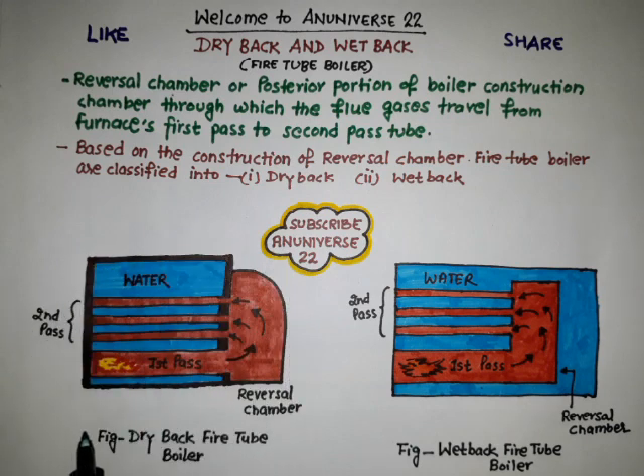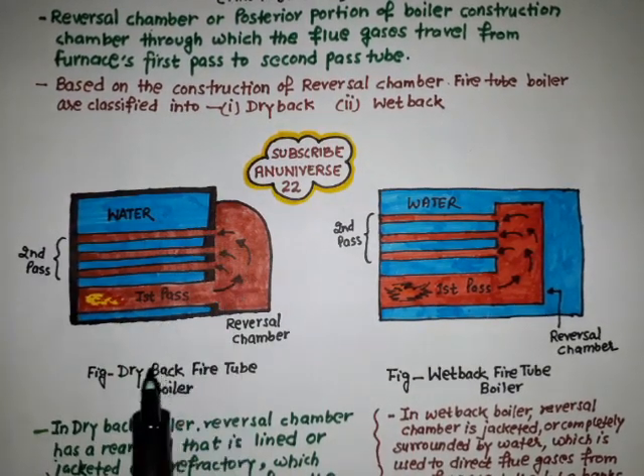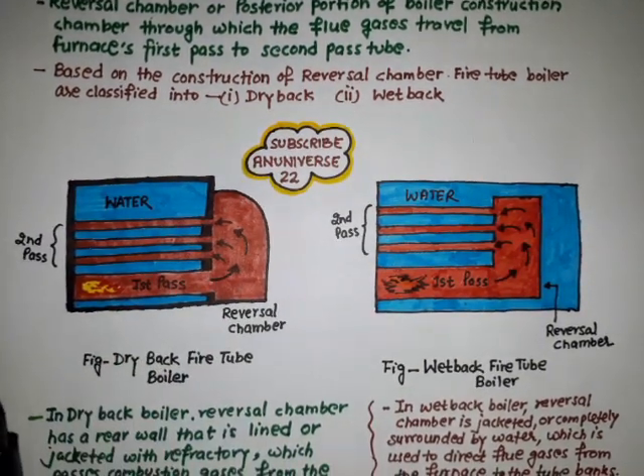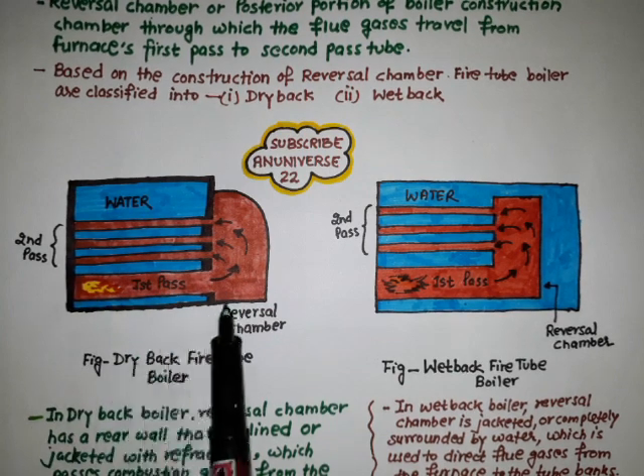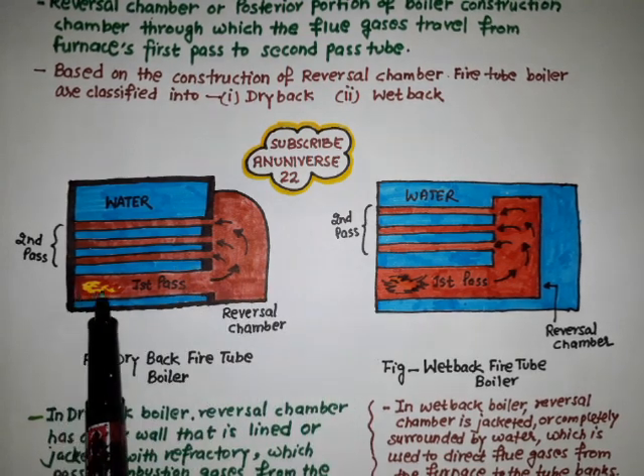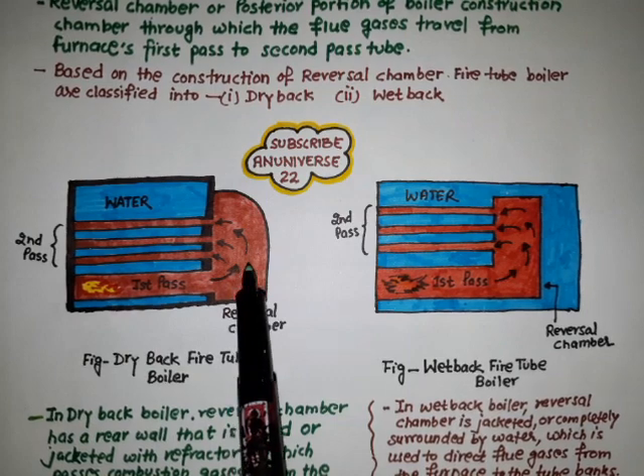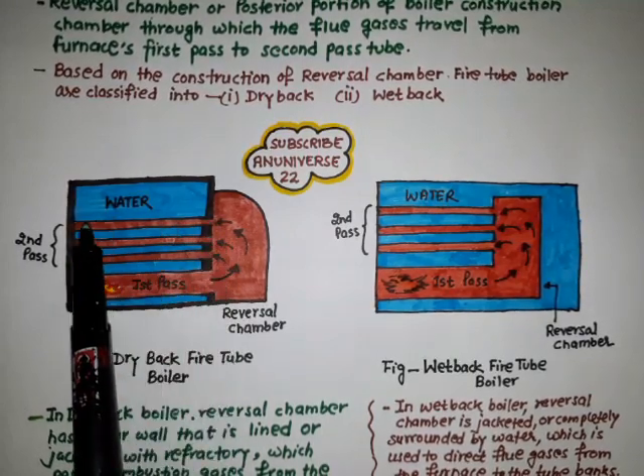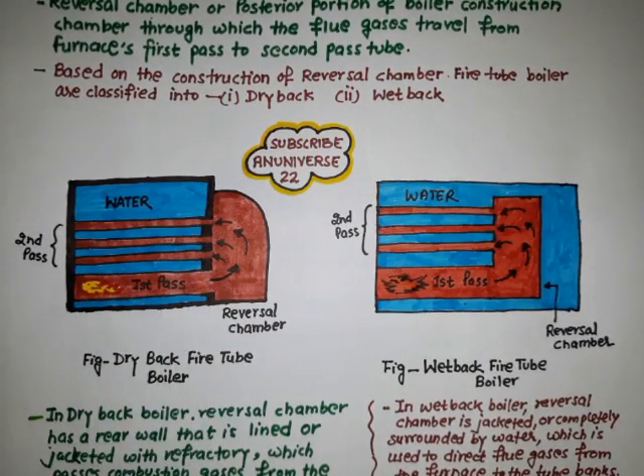Here we can see the diagram of the dry back fire tube boiler. It has a reversible chamber at the rear wall that is lined or jacketed with refractory, which passes the combustion gases. This is the furnace through which the flue gases come first. They are collected in the reversible chamber, and from the reversible chamber in the second pass, these gases move into the tubes. The red color indicates the flue gases and the blue color indicates the water.